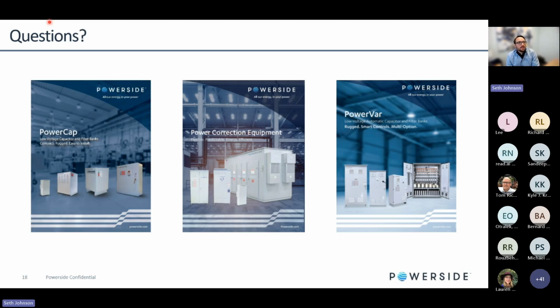Sure. Yeah, thank you for the question, Charles. So there's many aspects to doing harmonic correction. One of them, you'll see a lot of VFD manufacturers are going to be putting line reactors on the front end of the variable speed drives. Those are usually 3% or 5% line reactors, or they go to an LCL filter, sometimes called a sine wave filter. These are all good standard practices, but again, you will see that these specifications and these companies will come out saying that the VFD meets IEEE 519 compliance, and the fact of the matter is there's no such thing as a piece of equipment that meets that standard.